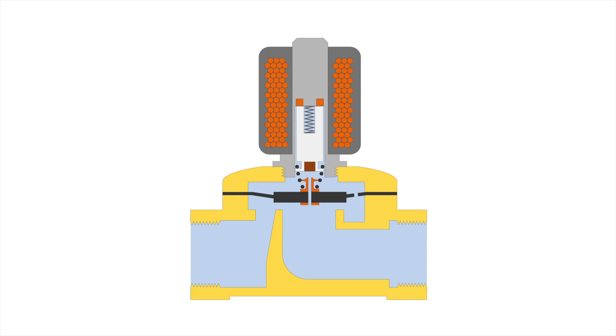As soon as the electric current is interrupted, the plunger will move down and lower the membrane and close the pilot port. The pressure in the upper chamber will rise and shut the valve off.